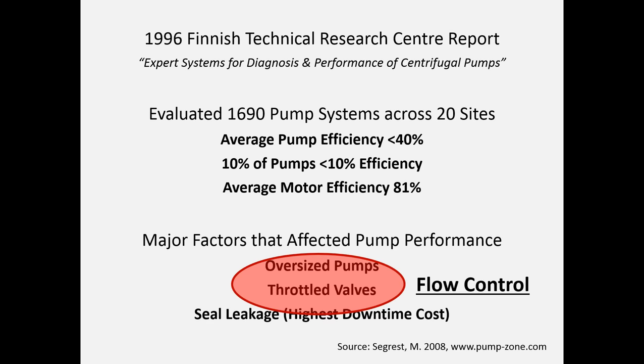That also has a flow-on effect into our maintenance and reliability. For example, seal leakage was found to be the highest downtime cost. That has to do with the additional forces created within the pump due to the fluid mechanics when we have a highly throttled pump. So we have an oversized pump which then has to be throttled in order to achieve the required flow rate, which then has these other flow-on implications into our system.